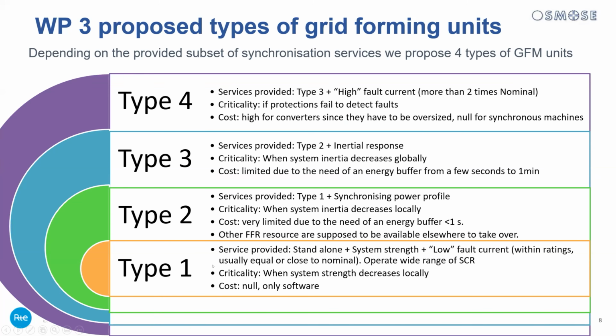So the first type is a standalone capability plus system strength, which means that if you have a voltage amplitude change, you will provide very fast current for a very short amount of time, and you can operate in a wide range of short circuit ratio. It's very interesting because basically it has no cost, it's only software update, and it's critical where you have low system strength locally.